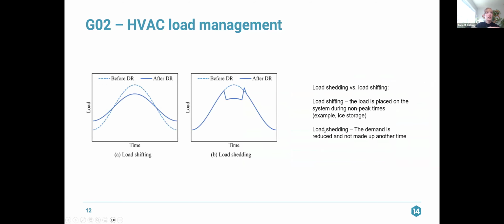As we're talking through this, I want to talk about the difference between load shedding and load shifting. Load shifting is the idea that we are cooling something down or heating something up before we are looking to reduce our peak demand. We want to make sure we're using the right language. It frustrated me as I was reading through this, because shedding versus shifting is a very common way to talk about demand in the controls world. And they talk about a cooling shift and a heating shift when really this is a shedding situation, not a shifting situation.